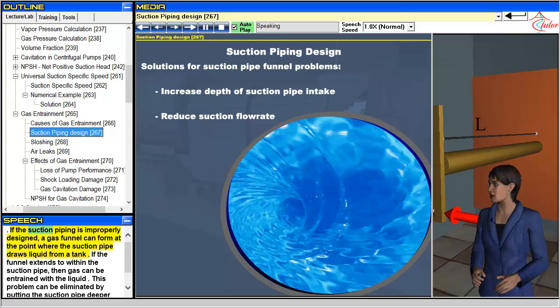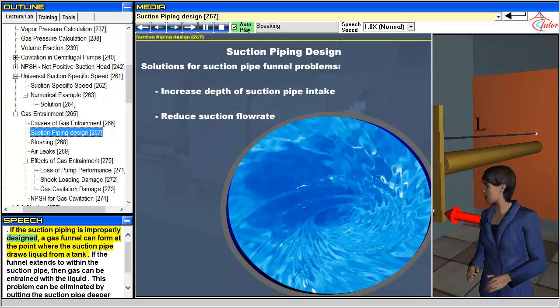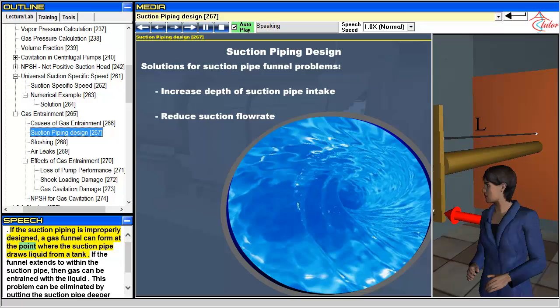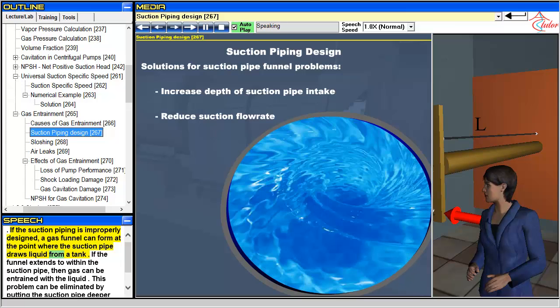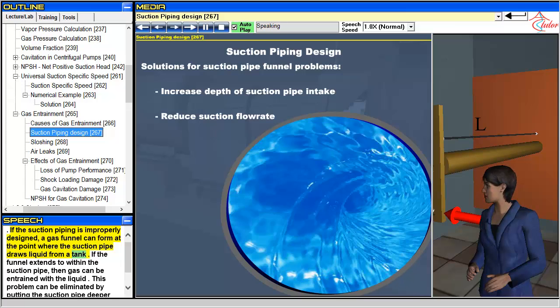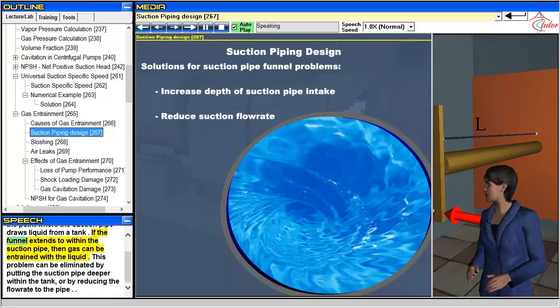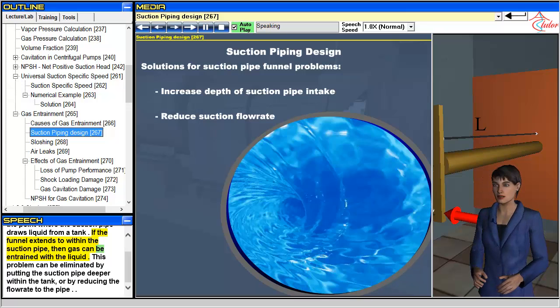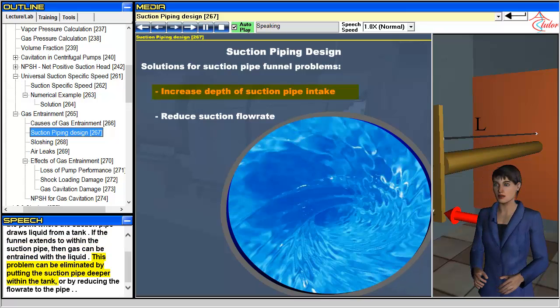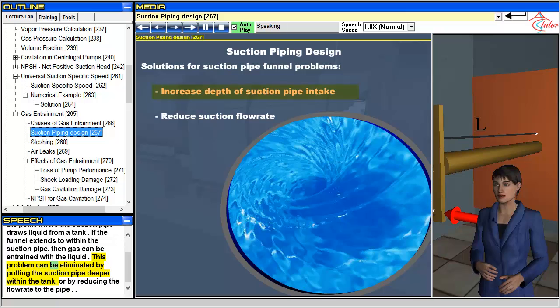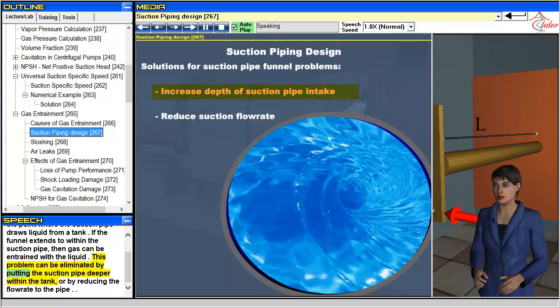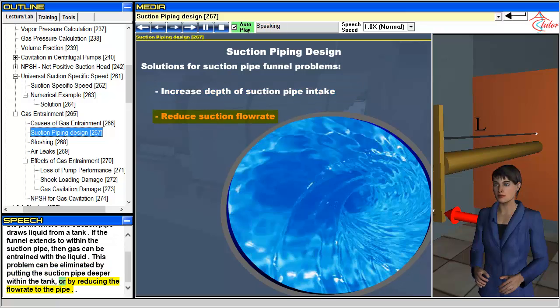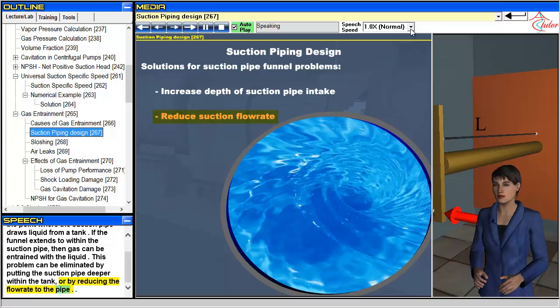If the suction piping is improperly designed, a gas funnel can form at the point where the suction pipe draws liquid from a tank. If the funnel extends to within the suction pipe, then gas can be entrained with the liquid. This problem can be eliminated by putting the suction pipe deeper within the tank, or by reducing the flow rate to the pipe.